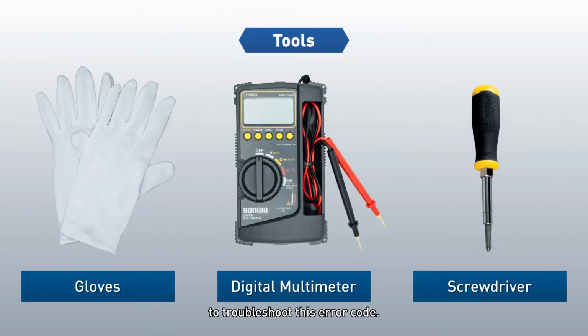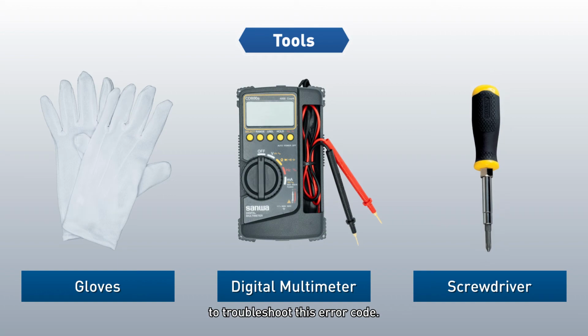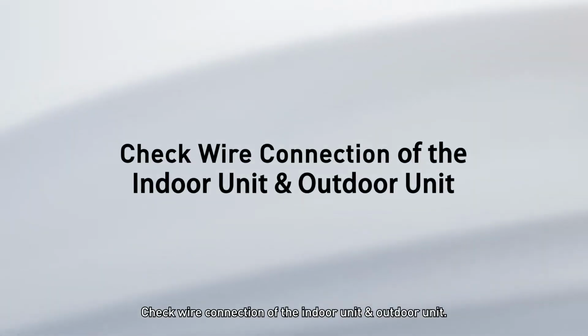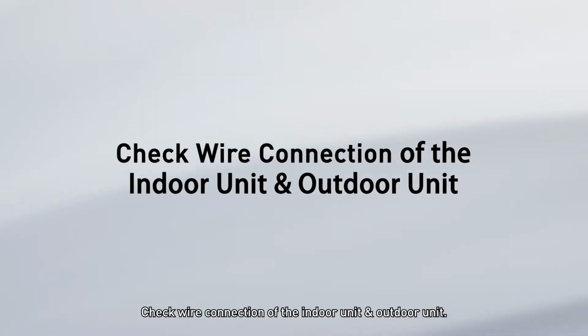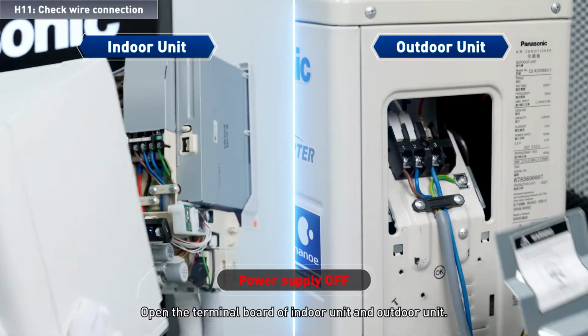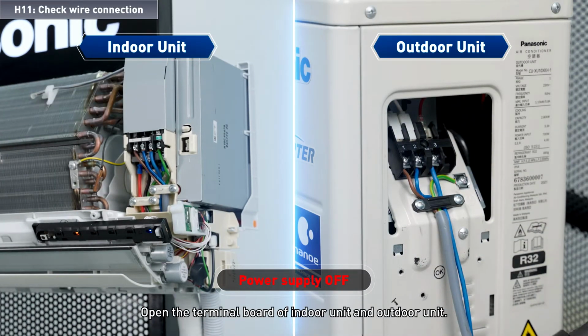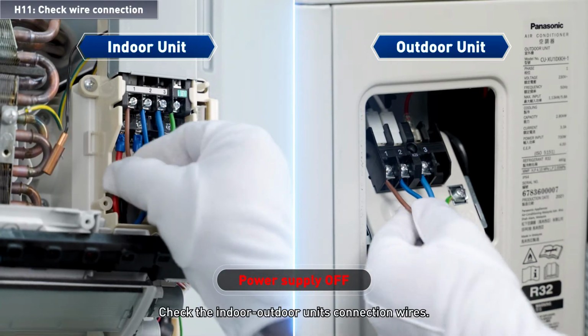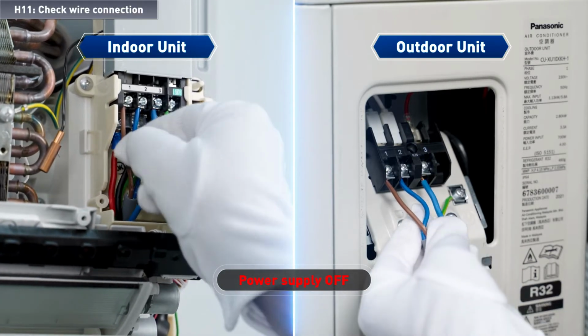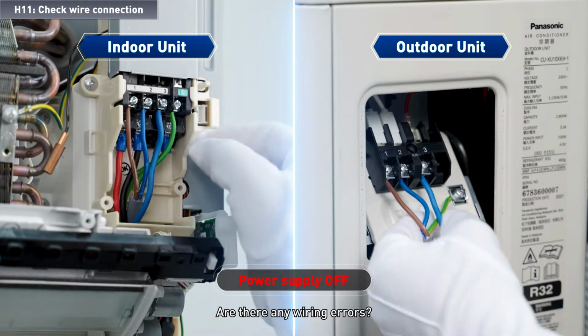Prepare the necessary tools to troubleshoot this error code. Check wire connection of the indoor unit and outdoor unit. Open the terminal board of indoor unit and outdoor unit. Check the indoor-outdoor unit's connection wires. Are there any wiring errors?